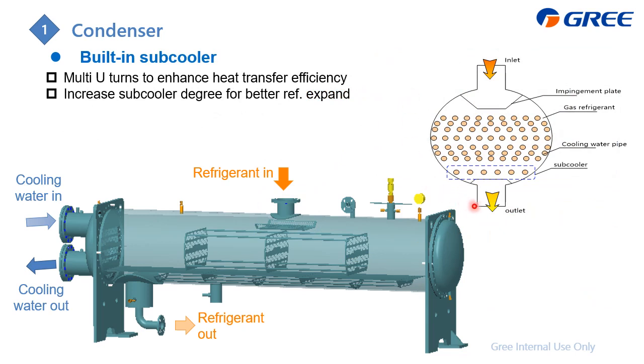This is the sectional view of this condenser. The gas refrigerant flows in from here, and then it will impact this plate to separate the oil, and then the gas will go through these pipes. Actually, inside these pipes is the cooling water, which cools down the gas, and then the gas will become liquid and accumulate at this area. And this area has the subcooler, which is this one. The purpose of this is to increase the subcooling degree for better performance when the refrigerant is expanded later. And then the liquid refrigerant will flow out from here.